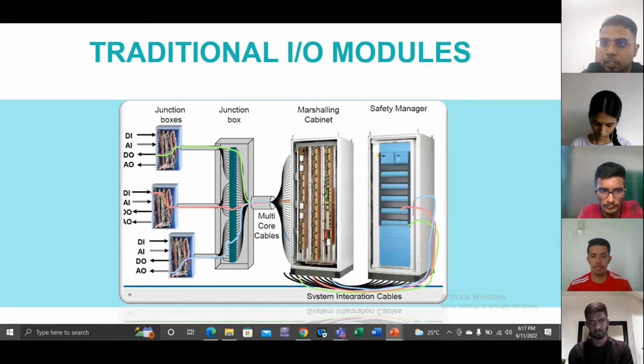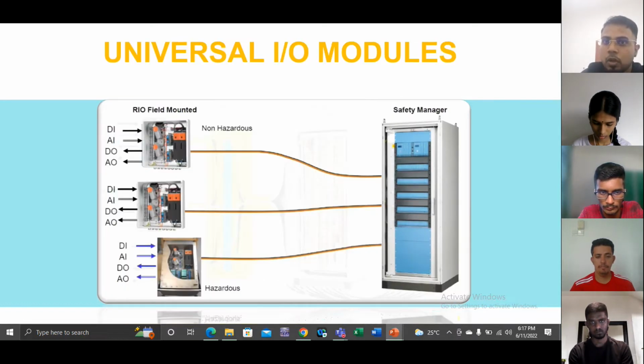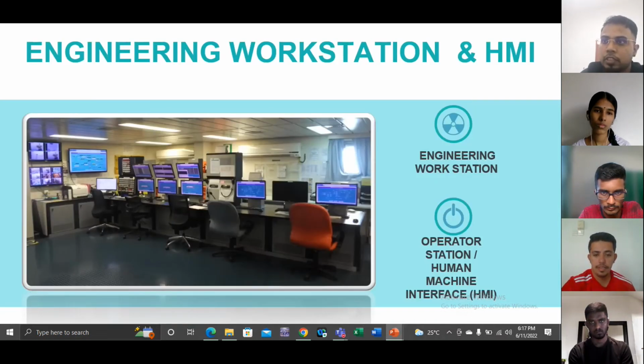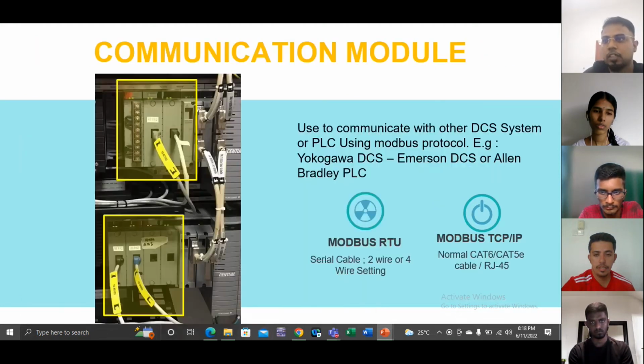Traditional I/O modules. This is the image of the traditional I/O module. We have a marshalling junction box, safety manager, system integration cables. Okay, next slide. This is the image of universal I/O modules. Next slide. Engineering workstation and HMI. Next slide. This is the communication module used to communicate with other DCS systems or PLCs using modules such as Modbus RTU and Modbus TCP/IP. Next slide.